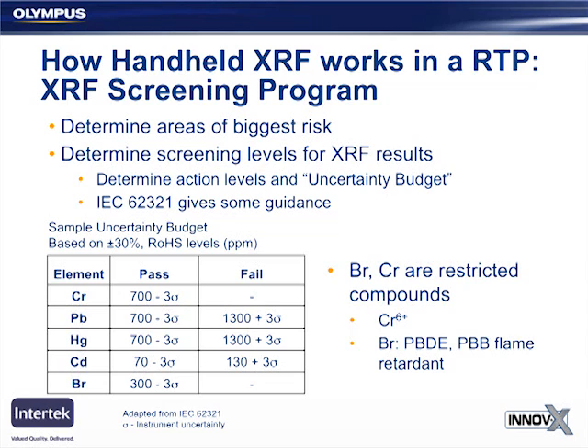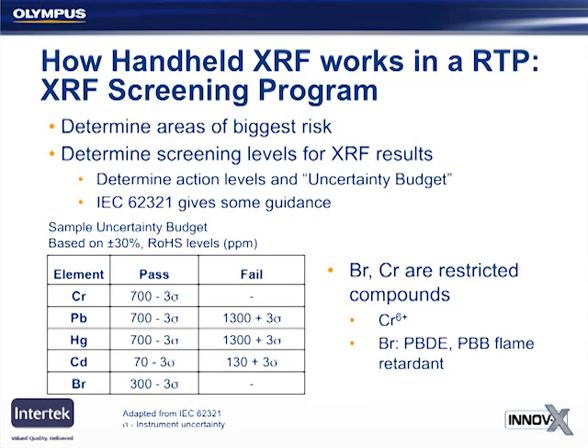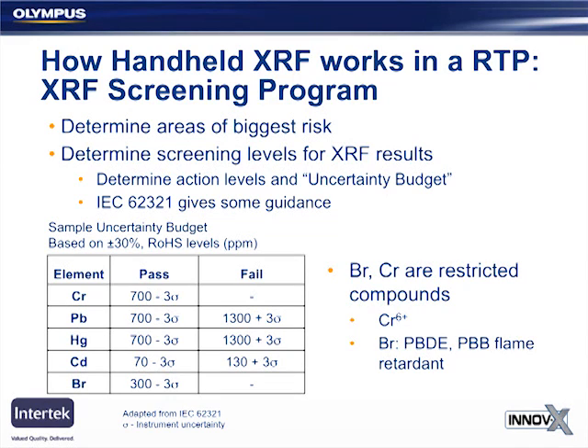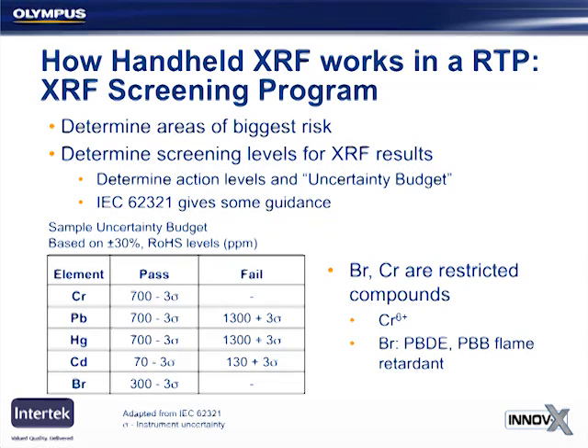You'll also need to determine screening levels. The XRF analyzer will give you a ppm or percent result for the elements that are present, but you need to decide how that result will translate into a pass or fail decision for that part or material or component. There are standard methods available to help you with that. As Joe mentioned, IEC 62321 is a pretty common one that gives some guidance on how to set up screening levels based on XRF results. And here's an example of one that's specifically for testing of homogeneous plastic materials under the RoHS regulations.